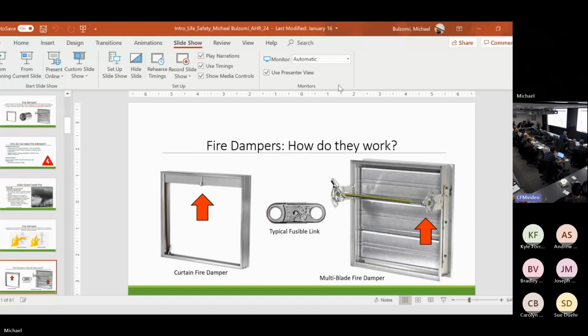It's a fusible link. So on the left is your curtain fire damper. Think of your blinds at home. You pull the drawstring on your blinds and they fall because of gravity. Same thing with this. That fusible link melts, that blade pack falls, gravity will pull it down. If the damper's in the wall in a vertical position, gravity pulls it down. I'm showing you a dynamic damper, and I'll get into the difference between dynamic and static.